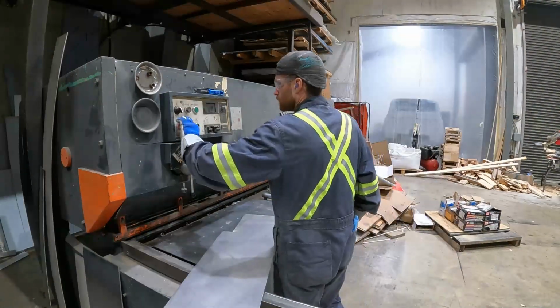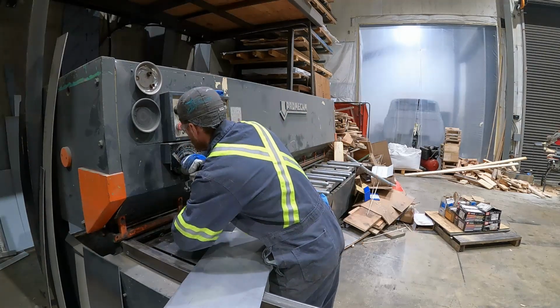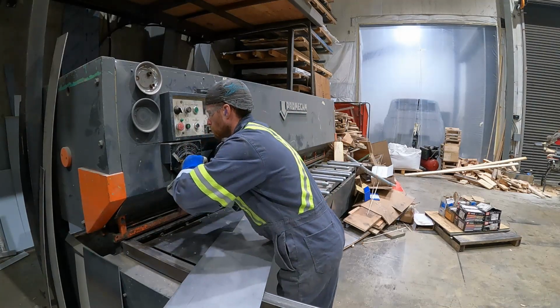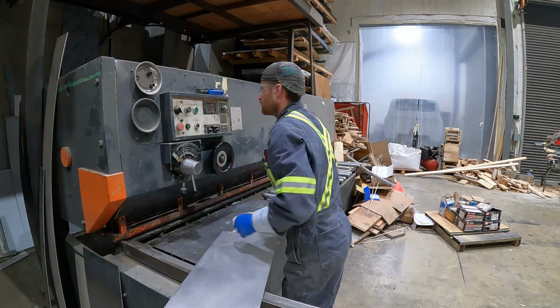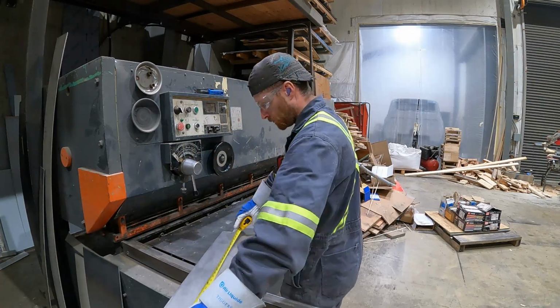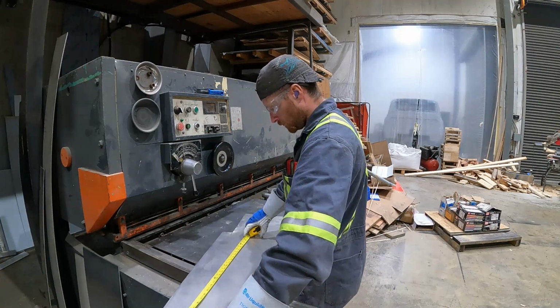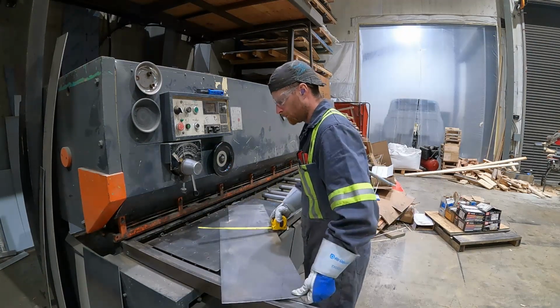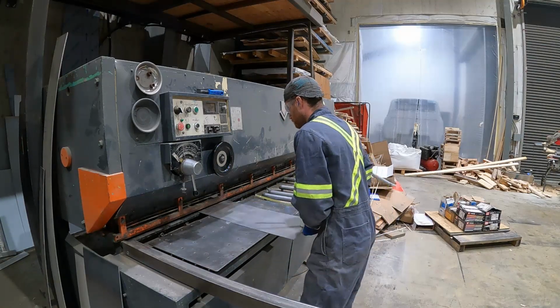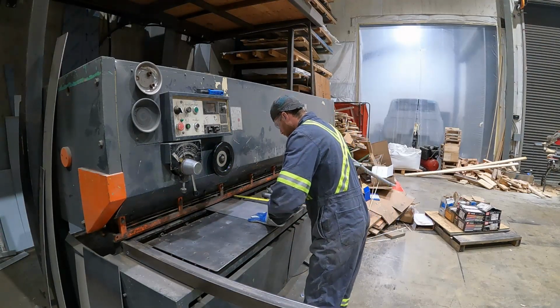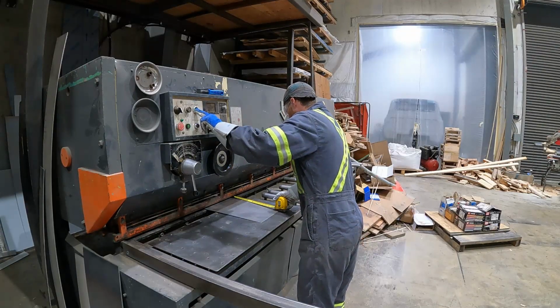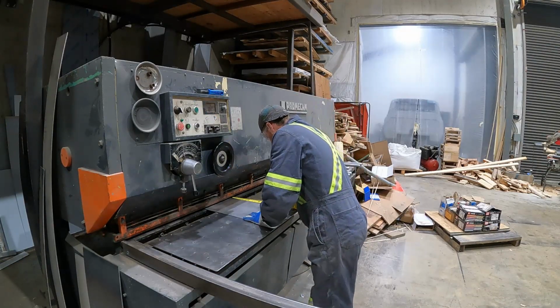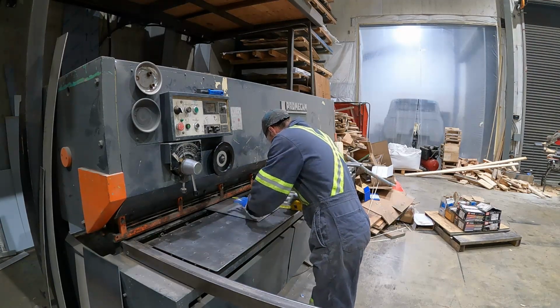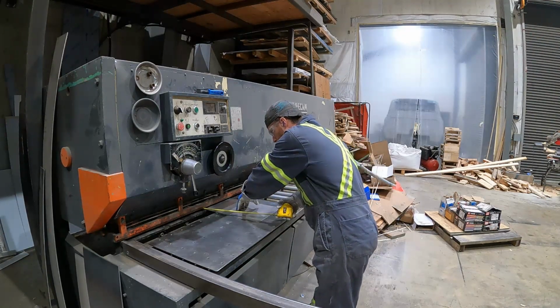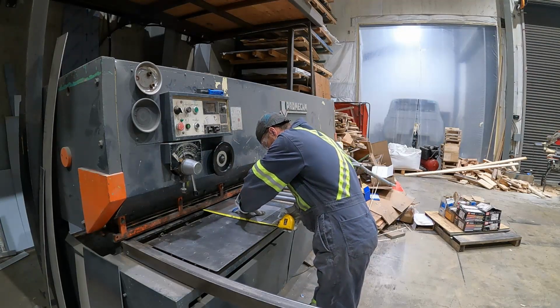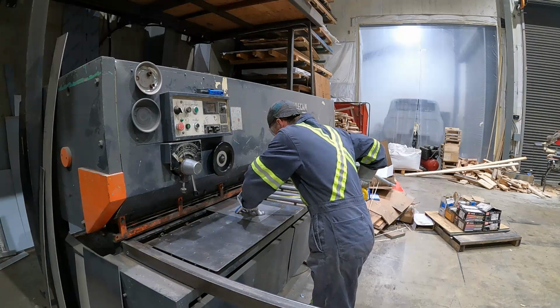Alright, so I stand corrected. The furnace is actually 6 1/16, and we need to go to 16 5/8 to fit that heat exchanger. So I'll have to do a couple sides that kind of flare out and then they flare back in. I'm going to make this out of some 18 gauge stainless steel 304 just because stainless wise I got lots of it. 18 gauge, I'd like something thin that I can still maneuver if the size isn't perfect. I can still fit it over the flange that's in there.